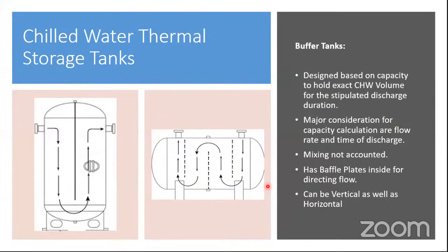Then there's also a category called buffer tanks. Buffer tanks can be vertical, they can be horizontal also, and they have baffle plates inside the tanks. A horizontal one can have three baffle plates, and a vertical generally has one. The design is based on the capacity to hold the exact chill water volume for the stipulated discharge duration. For example, if we are planning for a 5 minute backup, the flow is multiplied by the duration, and that's how the volume is arrived at. And this tank is exactly of that volume. So major considerations for capacity calculation are flow and the time of discharge. The mixing, the stratification that we were talking about in the stratified tank, is not accounted for in this tank.